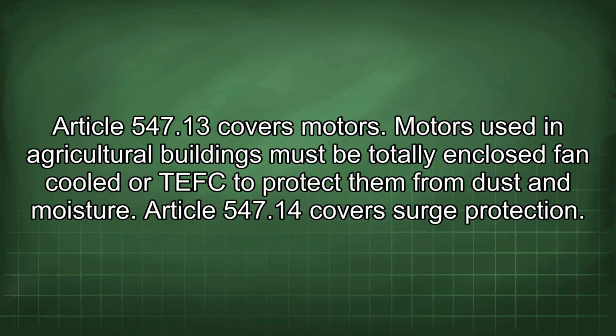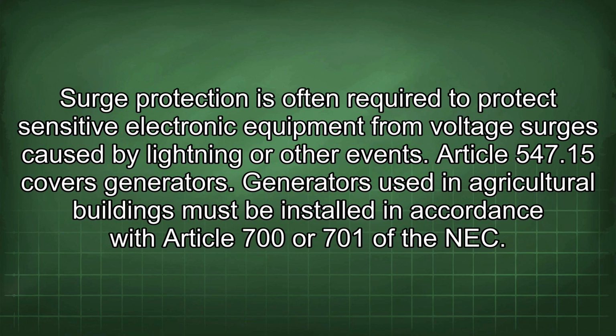Article 547.13 covers motors. Motors used in agricultural buildings must be totally enclosed, fan-cooled, or TEFC to protect them from dust and moisture. Article 547.14 covers surge protection. Surge protection is often required to protect sensitive electronic equipment from voltage surges caused by lightning or other events.